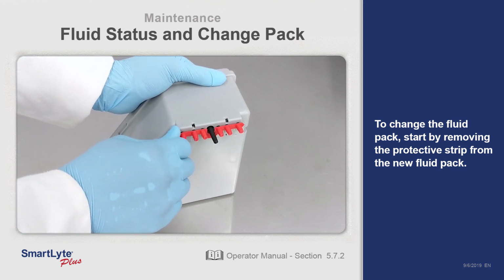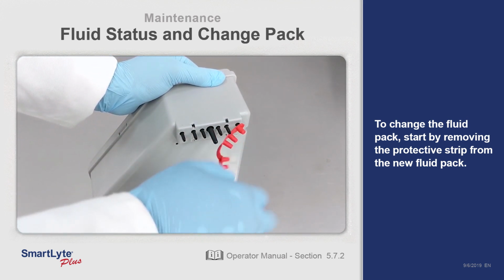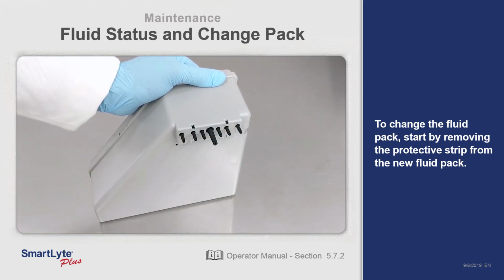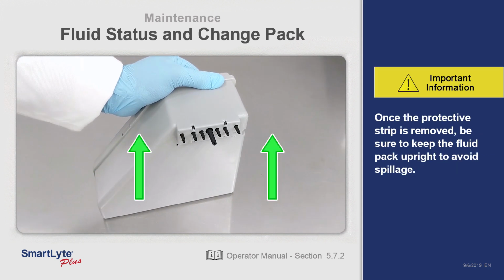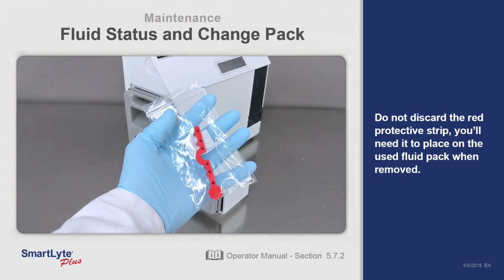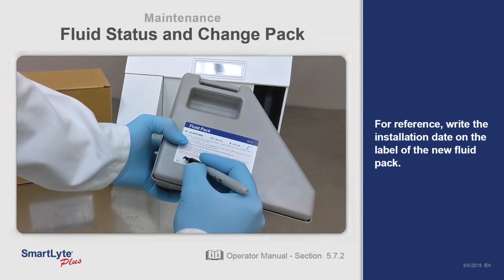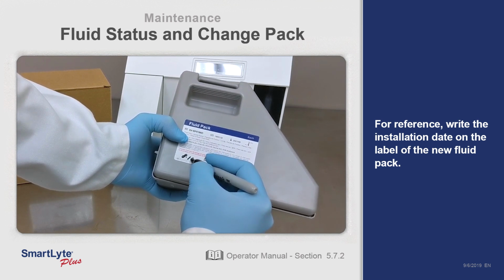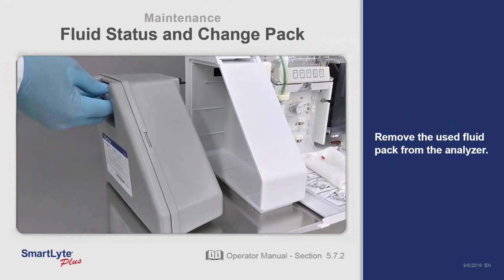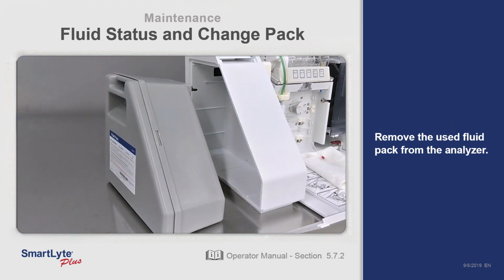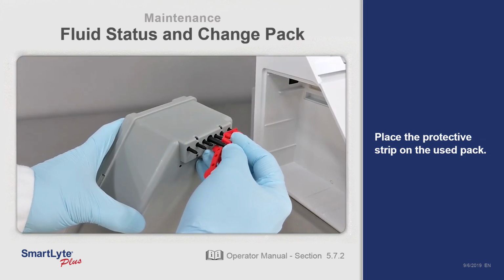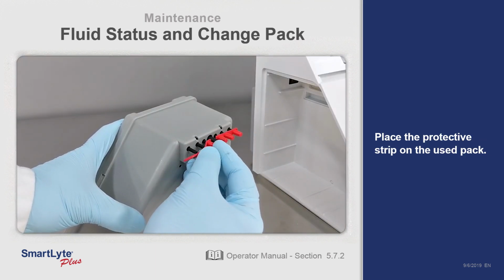To change the fluid pack, start by removing the protective strip from the new fluid pack. Once the protective strip is removed, be sure to keep the fluid pack upright to avoid spillage. Do not discard the red protective strip. You'll need it to place on the used fluid pack when removed. For reference, write the installation date on the label of the new fluid pack. Remove the used fluid pack from the analyzer. Place the protective strip on the used fluid pack.